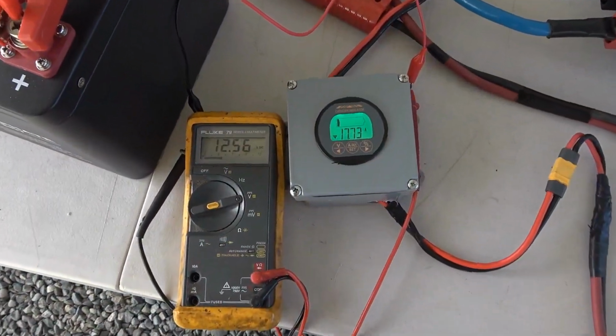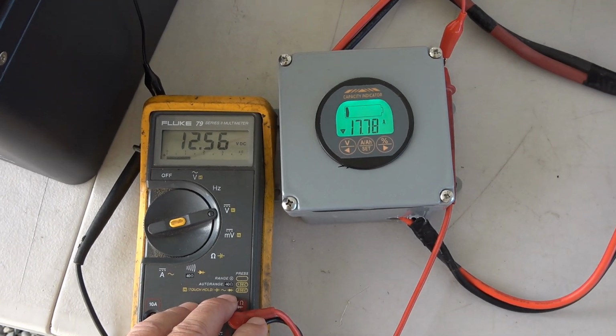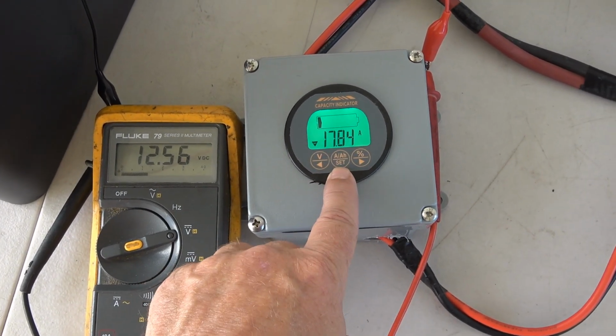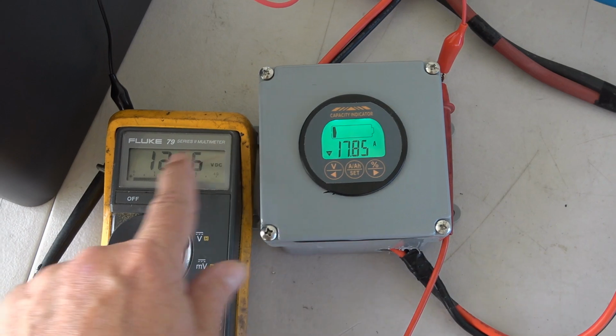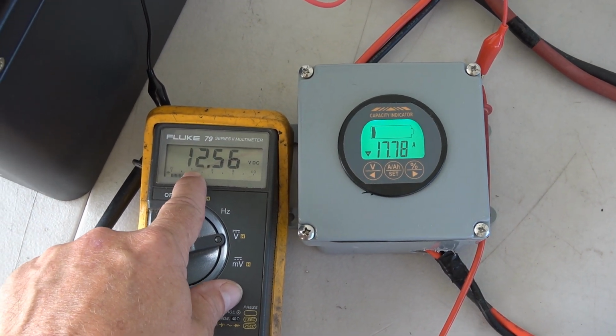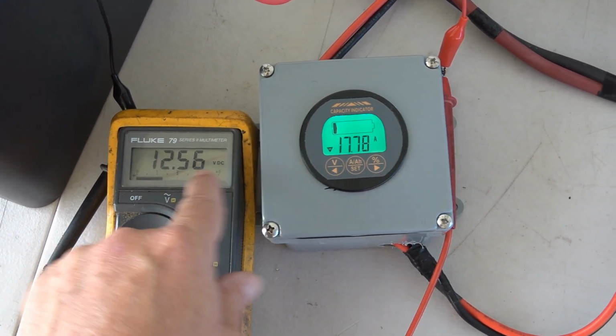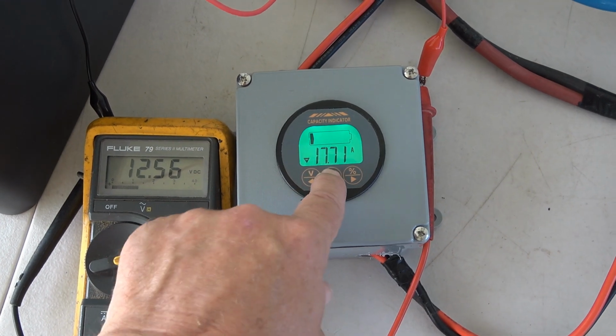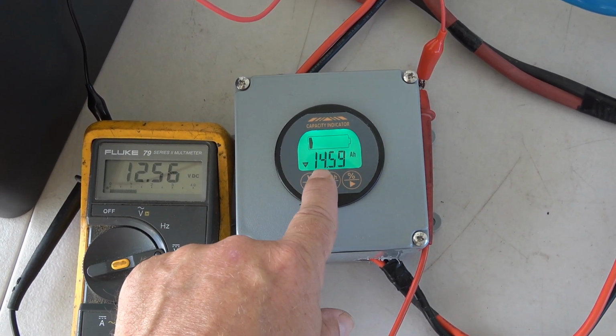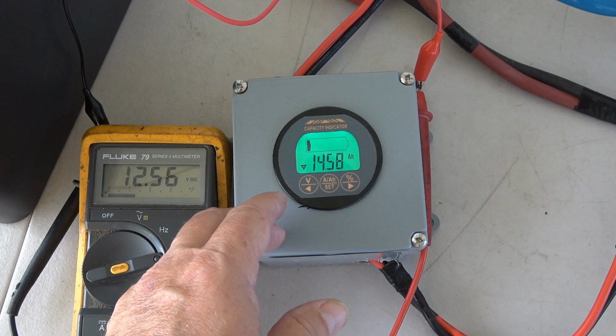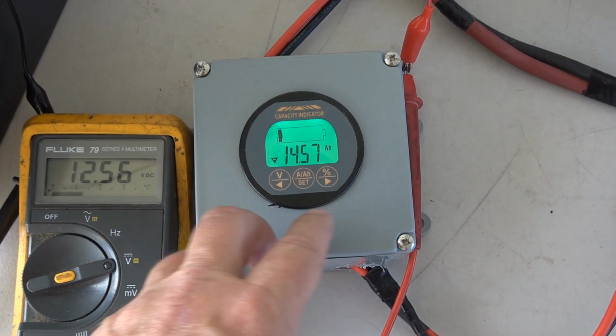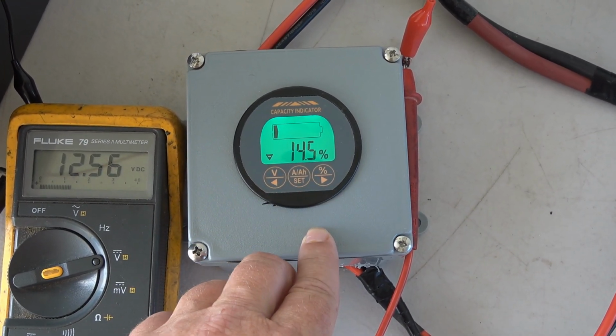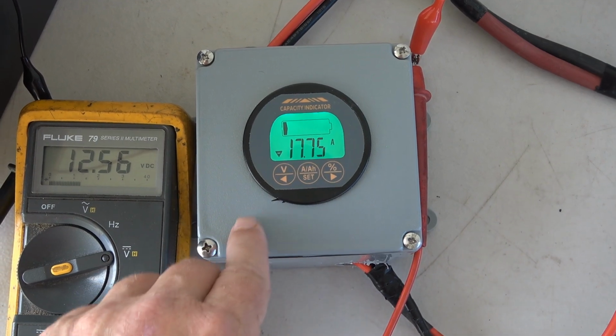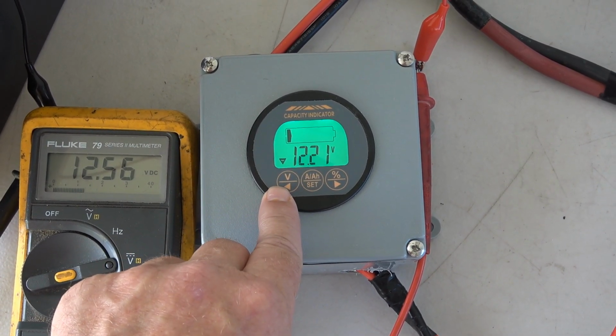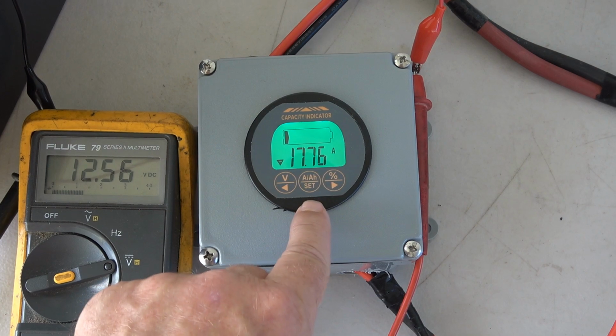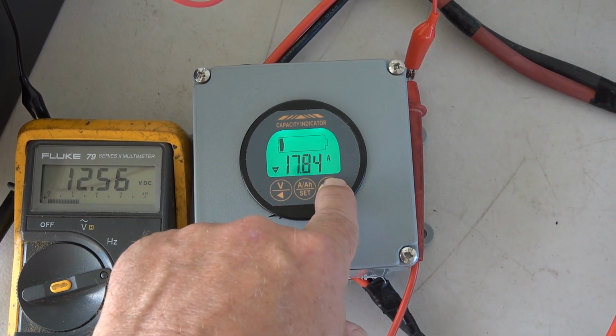Okay, checking in at the 300-minute mark, 5 hours later, still drawing 17 amps. Voltage on the terminals of the battery is 12.56, and it says a little over 14 amp hours left, 14.5%. So we'll let it go, see if we can get the 100 amp hours out of it.